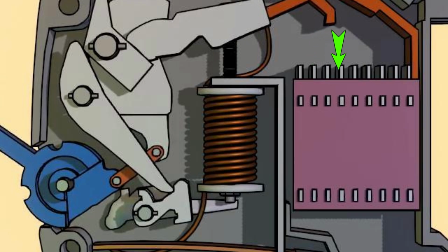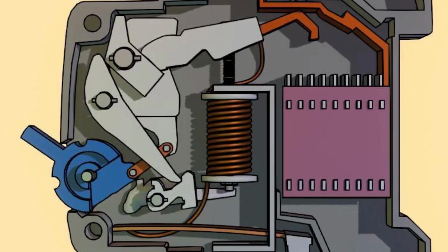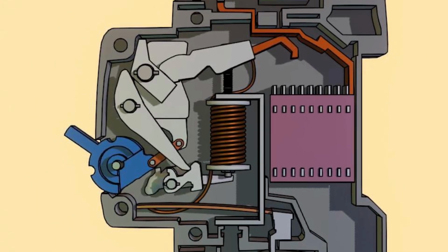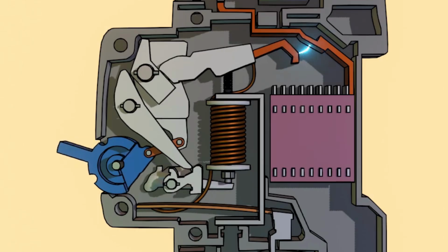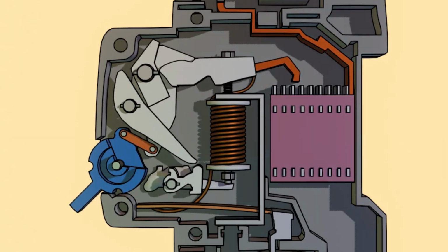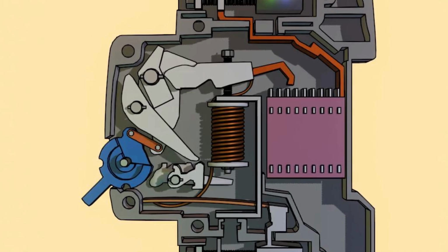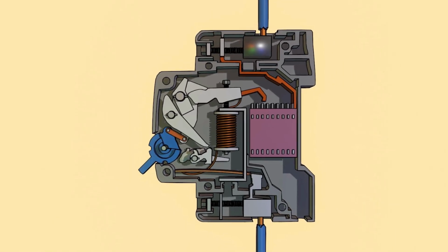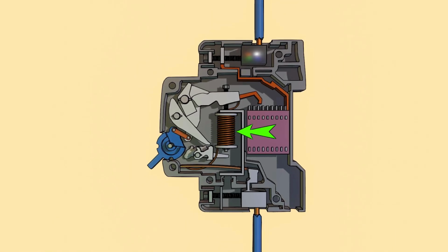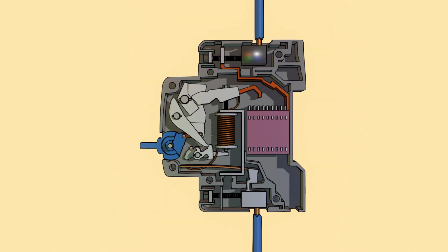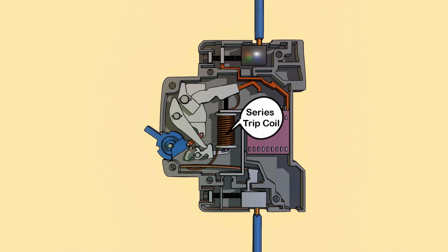These are the arc splitters. When an arc forms during contact separation, due to the special shape of the contacts, the arc moves towards the splitter, gets divided, and extinguishes. Now see the tripping arrangement for short circuit faults. This is the tripping coil. It is connected in series with the circuit. So this mechanism is called a series trip mechanism, and this coil is called a series trip coil.